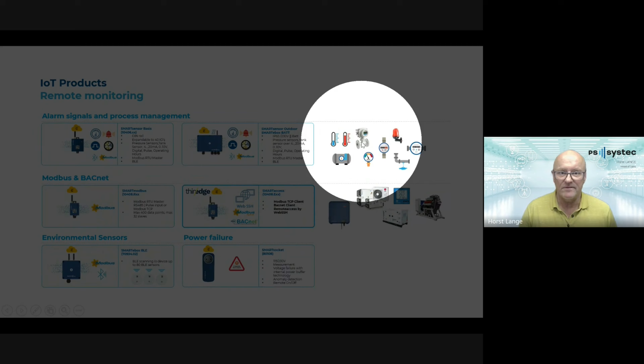If you look at the remote monitoring part, we can connect any kind of sensor. On the right side, it should be compatible with PT1000, volt, or milliampere. Every sensor out there, and there are millions, we can connect. We use alarm contacts, any Modbus device, valves, flow meters, leakage, any gauge like pressure or temperature, power fail outage, for example.